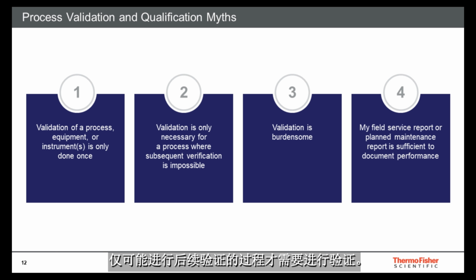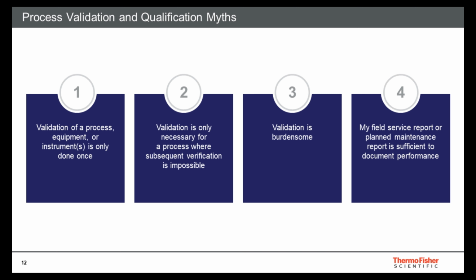On to myth 2: validation is only necessary for processes where subsequent verification is impossible. Validation should be considered even if your process includes 100% verification. 100% verification is not necessarily 100% effective in a process. Myth number 3 is that validation is burdensome. Yes, validation can be burdensome and costly, but planning is key to mitigation of this point. Validation is also an investment in the process, equipment, instrumentation, and personnel. It helps you understand the controls necessary to reduce variability. Reducing variability reduces risk to results and products from the process and reduces operational costs. A well-planned process validation improves customer satisfaction and confidence.